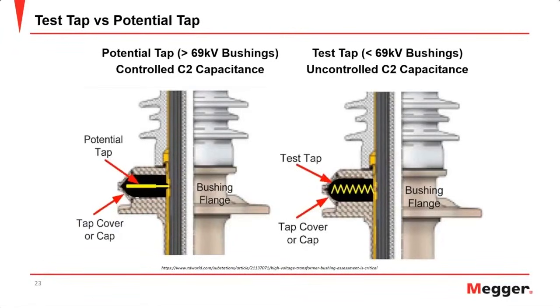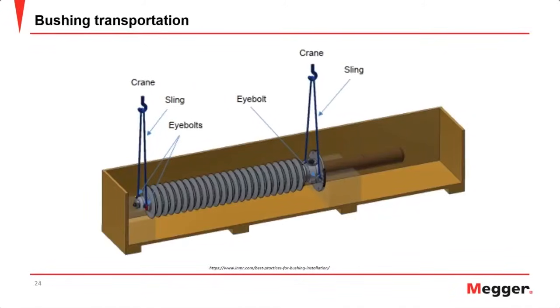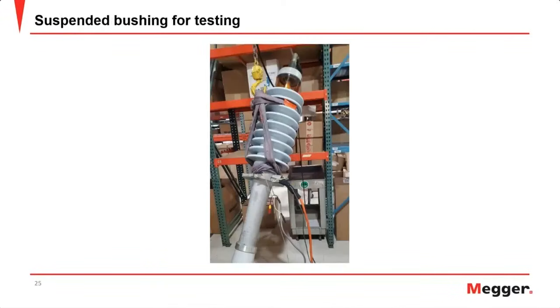One important consideration for bushings, in particular OIP, is that when they are transported, they will be lying on their side, and that will cause the oil to flow in ways that can impact the measurements of this bushing. So it's important that after receiving a bushing and before you start your commissioning work, these bushings must be suspended or oriented in a particular way, so that the oil is doing its job inside the bushing.